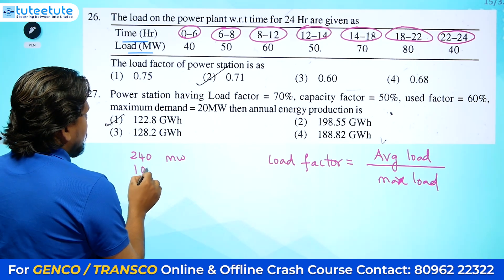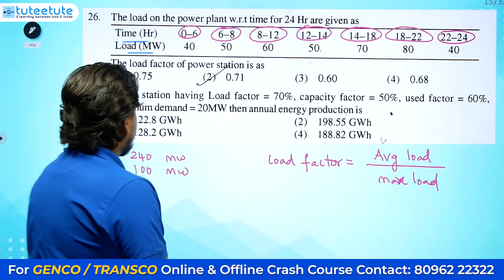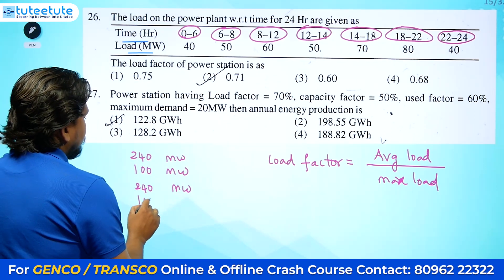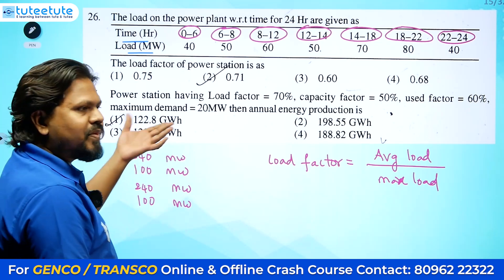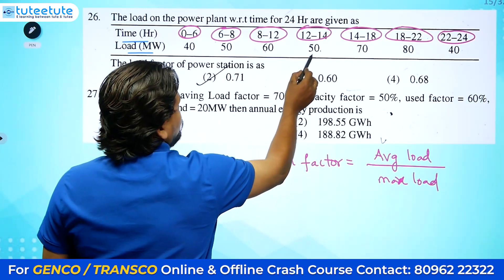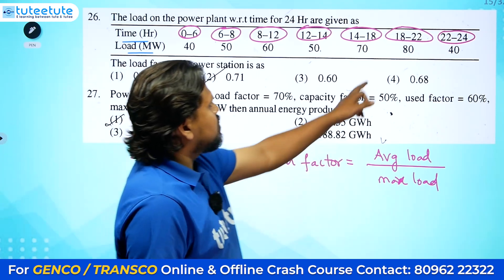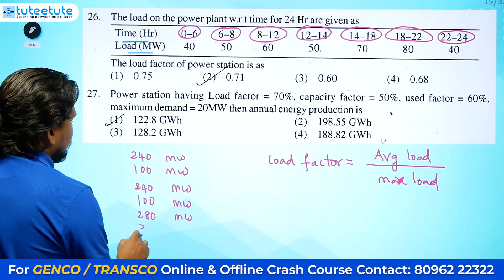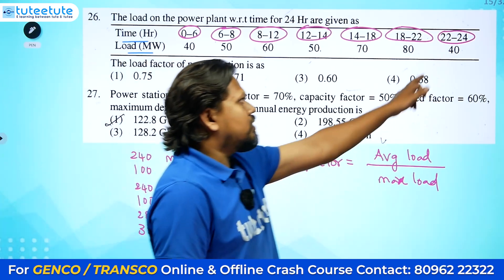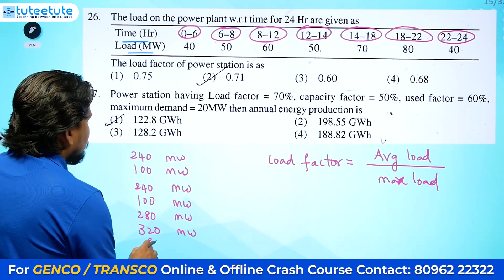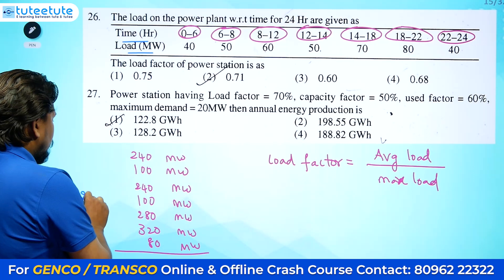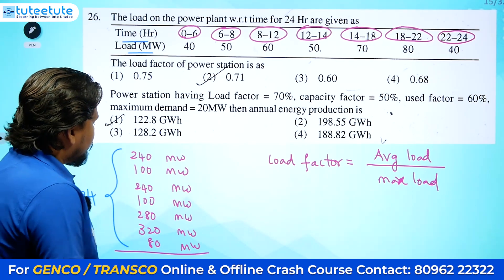For 50 MW for 2 hours: 100 MWh. For 60 MW for 4 hours: 240 MWh. Again 50 MW for 2 hours: 100 MWh. I am calculating the entire load for the day. For 70 MW for 4 hours: 280 MWh. For 80 MW for 4 hours: 320 MWh. For 40 MW for 2 hours: 80 MWh. This is the complete load for the entire 24-hour day.